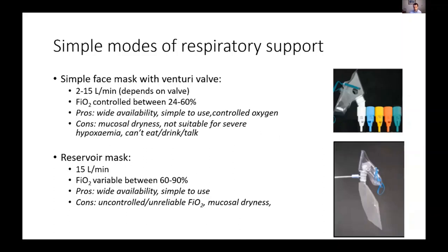For some reason, this picture is slightly out of order. In any case, the blue is at 24%, the white 28%, yellow 35%, red 40%, and green 60%. They'll all have a number with litres per minute on it, and that's what you need to set the oxygen flow rate to from the wall.